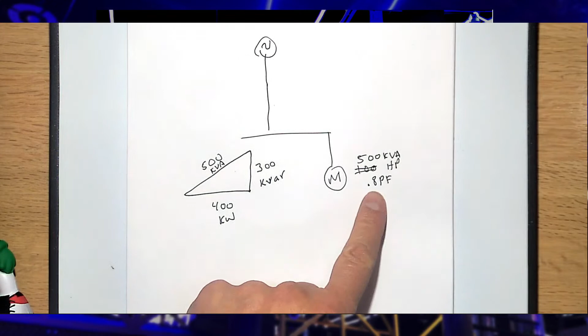Now, if I wanted to show you how a capacitor works, I could put a capacitor on here, let's say 300 kVAR to make it easy. Then the equal and opposite shows up, and my power triangle isn't a triangle anymore, it's just a flat line: 400 kilowatts, 400 kVA, and 0 kVAR.